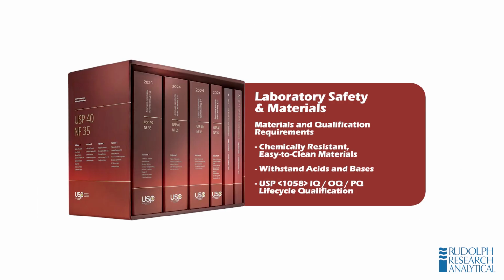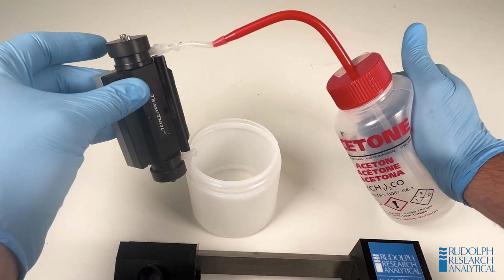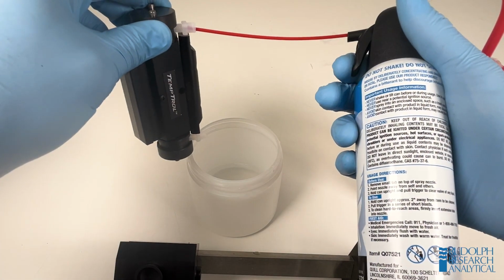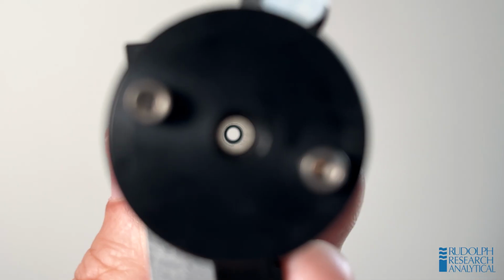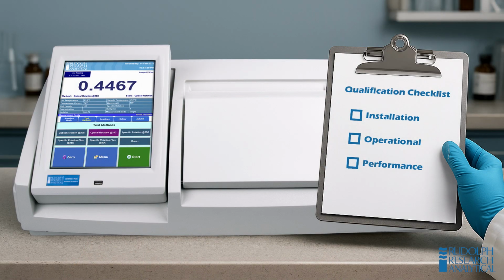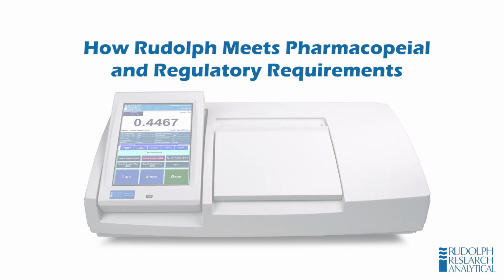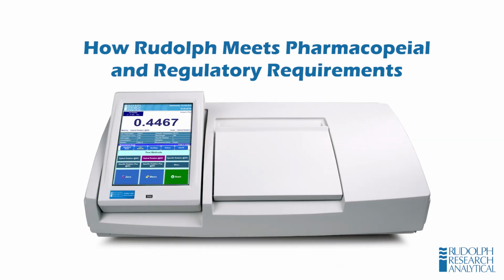In addition to calibration and temperature, laboratory safety and materials are part of compliance. All sample contact materials must be chemically resistant and easy to clean, capable of withstanding strong acids and bases. Finally, under USP 1058, every instrument must go through full qualification, installation, operational, and performance testing to prove consistent performance over its life cycle. Now, let's look at how Rudolph Research Analytical helps you meet and exceed all of these requirements with the Autopol 5+ and Autopol 6.